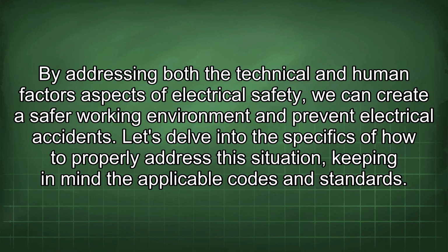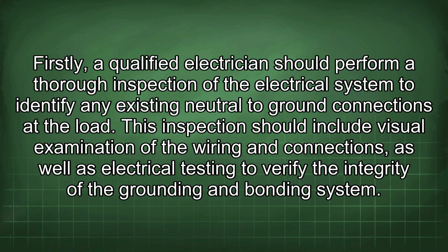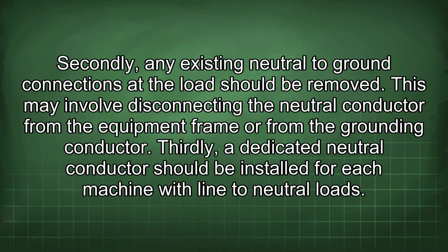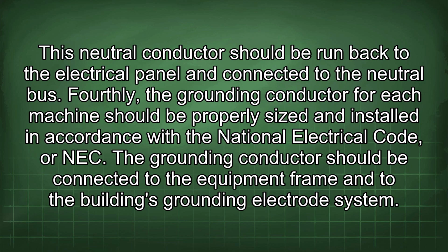codes and standards. Firstly, a qualified electrician should perform a thorough inspection of the electrical system to identify any existing neutral to ground connections at the load. This inspection should include visual examination of the wiring and connections, as well as electrical testing to verify the integrity of the grounding and bonding system. Secondly, any existing neutral to ground connections at the load should be removed. This may involve disconnecting the neutral conductor from the equipment frame or from the grounding conductor. Thirdly, a dedicated neutral conductor should be installed for each machine with line to neutral loads. This neutral conductor should be run back to the electrical panel and connected to the neutral bus.